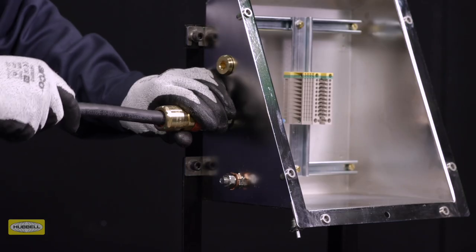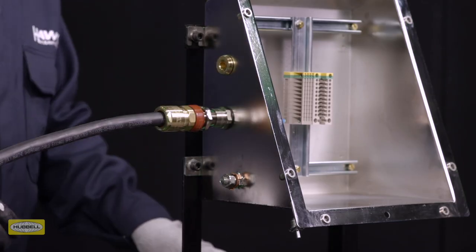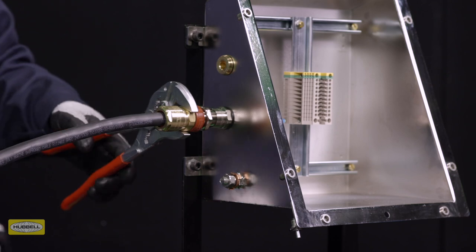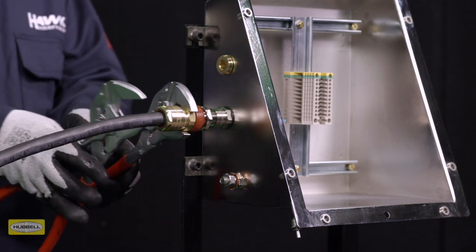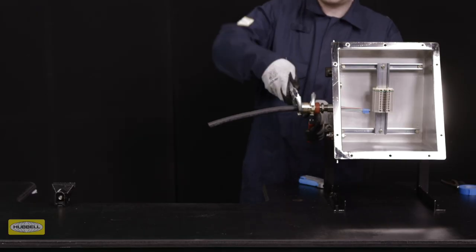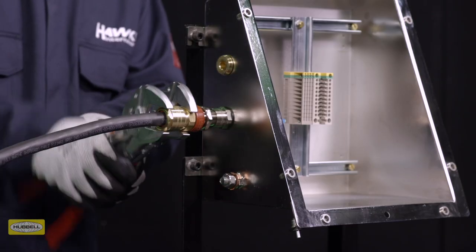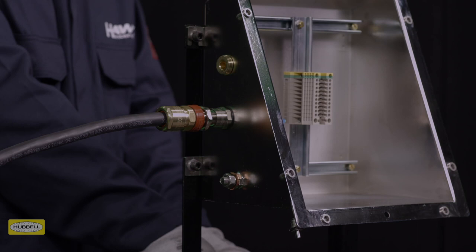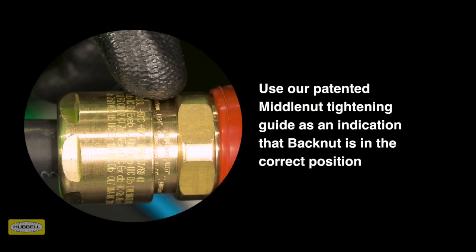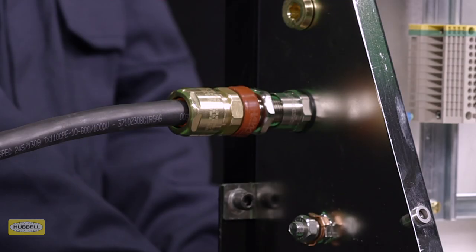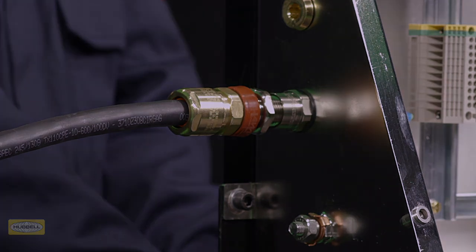Hand tighten the backnut until the seal is formed around the cable. Use a wrench or spanner to grip the middle nut while preventing the middle nut from turning. Use a second wrench to apply one further full turn to the backnut. Use our patented middle nut tightening guide as an indication that the backnut is in the correct position to suit cable diameter. A diameter scale is provided in our assembly instructions to help with this process. Installation is complete.